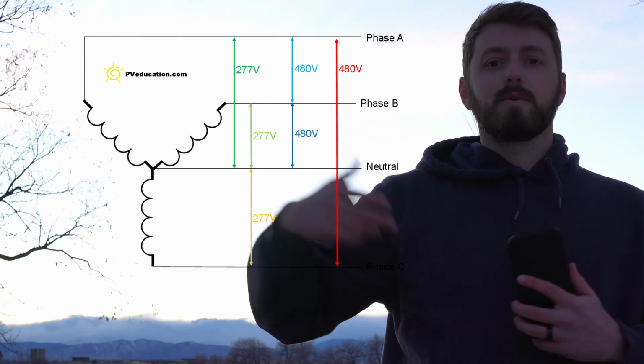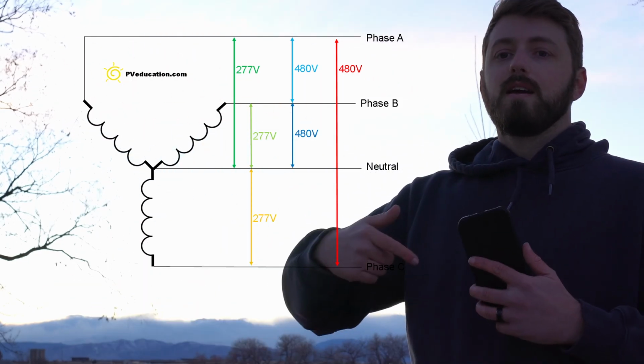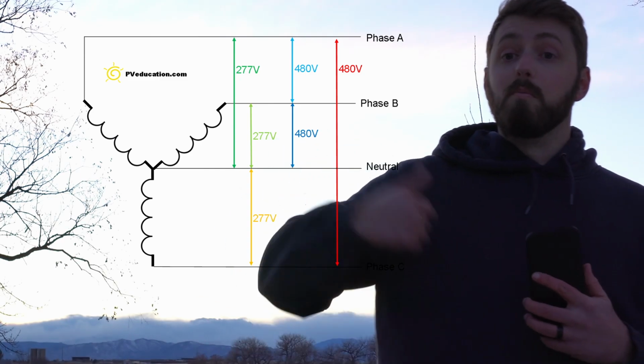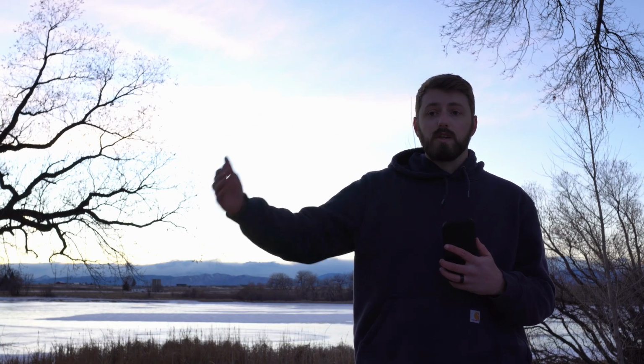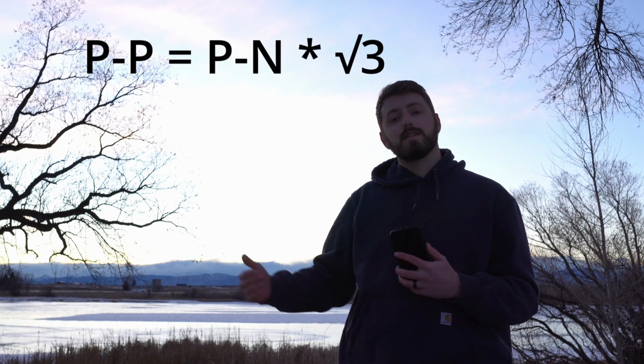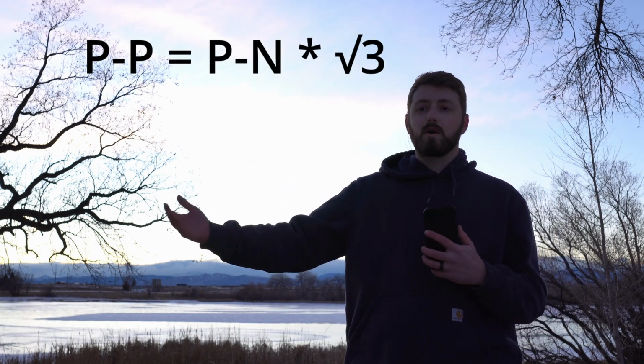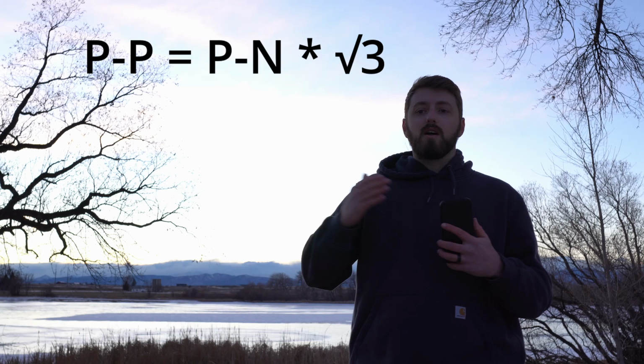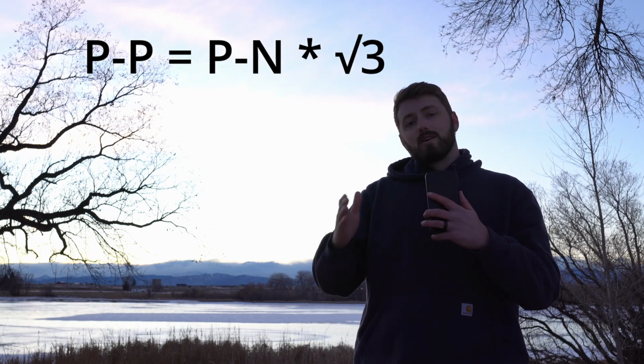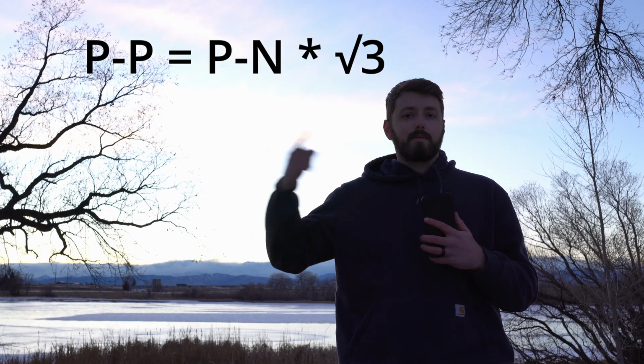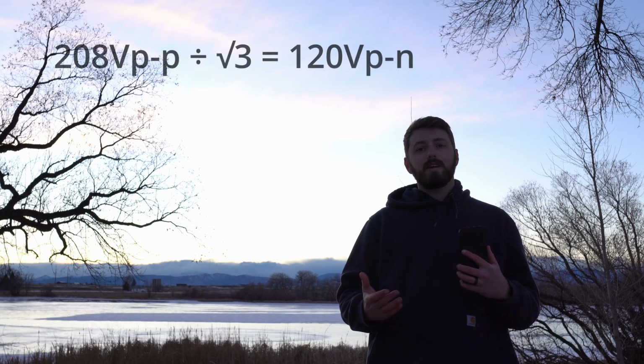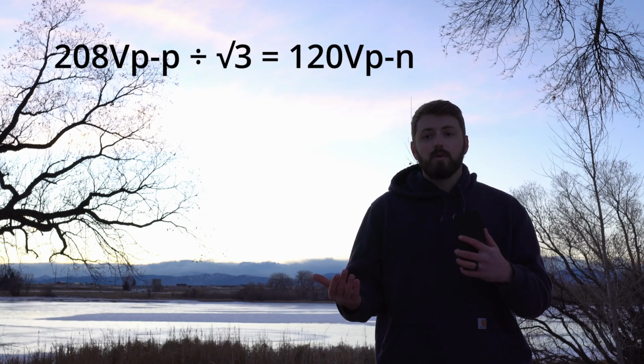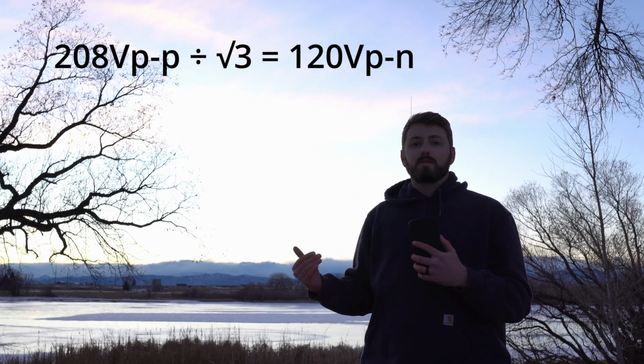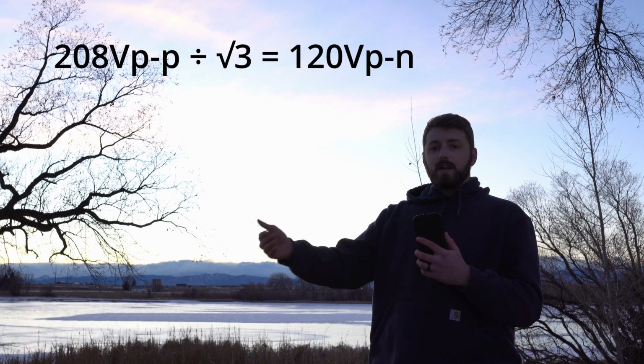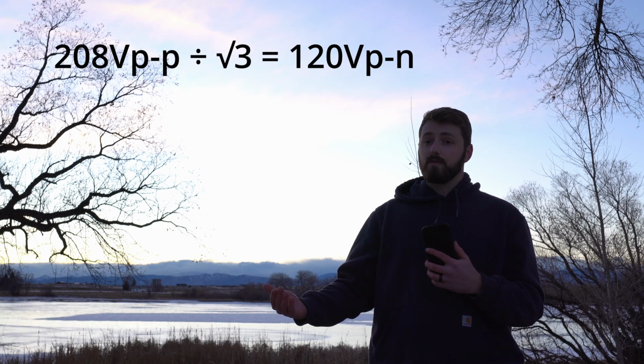But if I take a measurement between A phase and B phase, I'll see 480 volts, which is more voltage. The ratio between the phase to neutral and a phase to phase voltage in this case is multiplied by the square root of 3, due to the phase angle offset between their sine waves, as they're a third of a full revolution away from each other. If I give you a phase to phase voltage of 208 volts, you can divide that by the square root of 3 and get the phase to neutral voltage of 120 volts.